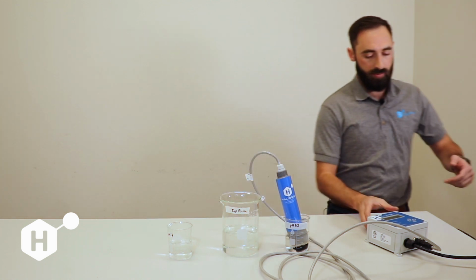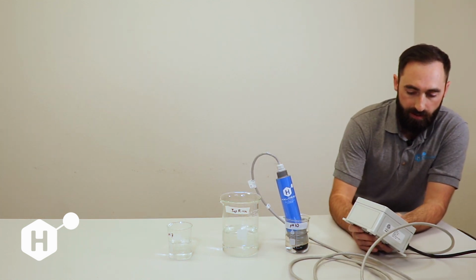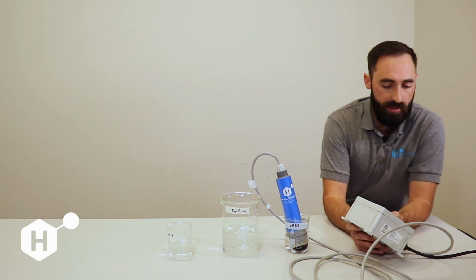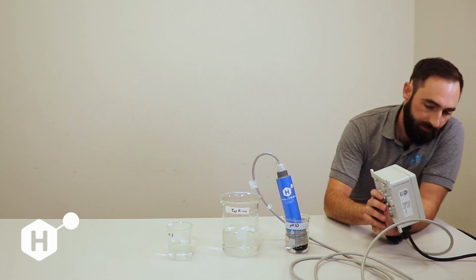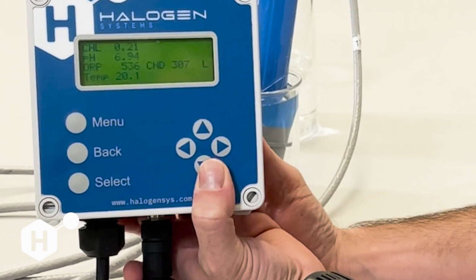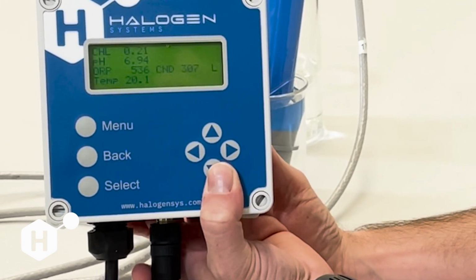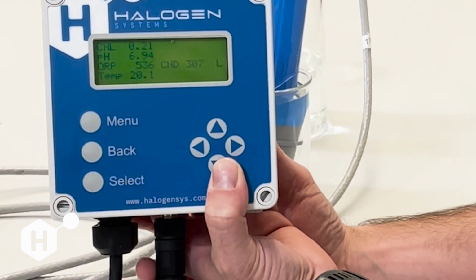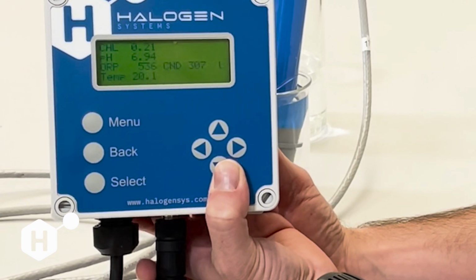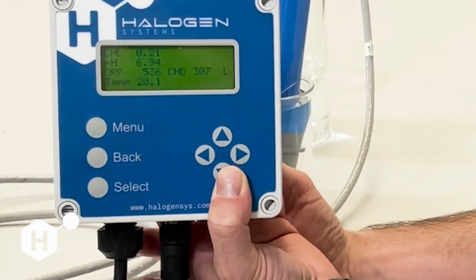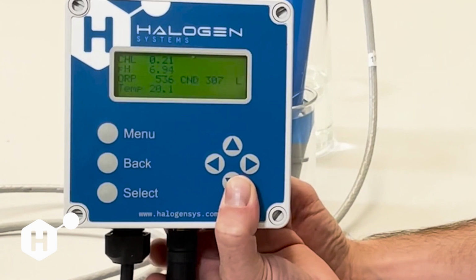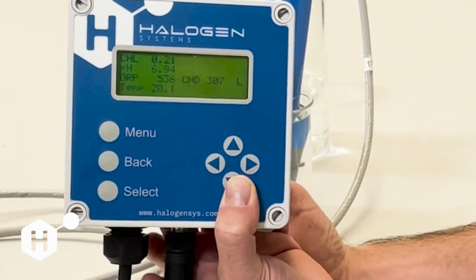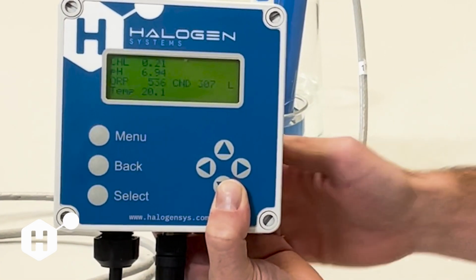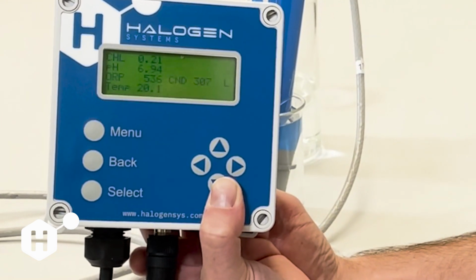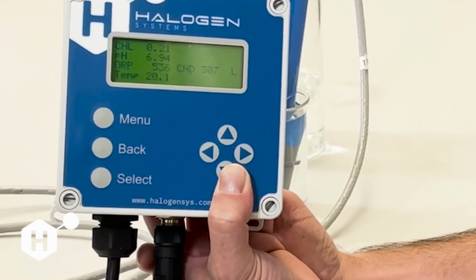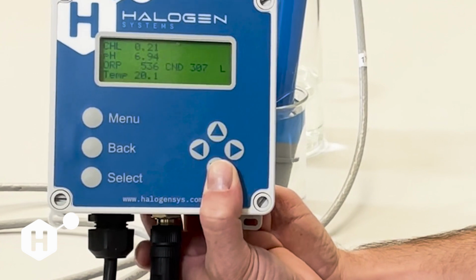And we're going to come over to our display again, and we're going to wait until we see that pH value change and start going up. And same thing as in the 7 buffer. I usually give it about 3 to 5 minutes to stabilize. Really at this point, you can't leave it in here too long. So if you're uncertain or if you need to go do anything else, go ahead and just let it run in this 10 buffer for a few minutes and then come back, and then you can do that 10 buffer calibration.